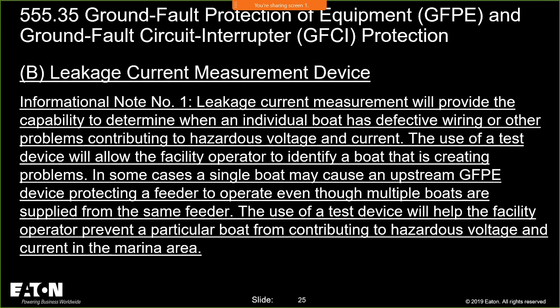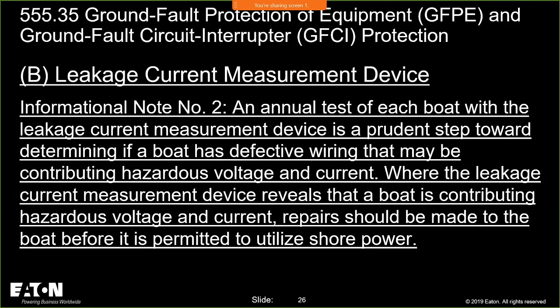So, leakage current measurement device again, and they have a description of what that is in an informational note. An annual test of each boat with the leakage current measurement device is a prudent step. Remember, informational notes cannot have requirements, but they can give you guidance, and this is where the head of this panel is at. They want to promote testing these boats, because the reason certain people passed away is not necessarily because of the wiring on the infrastructure, but because of the boat that pulled into that dock and plugged in.